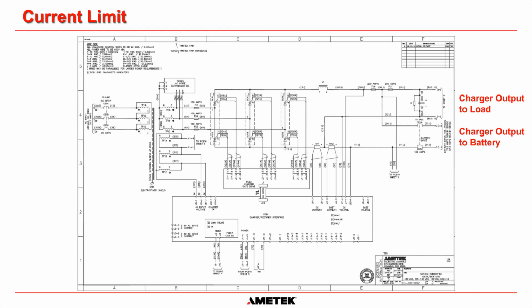And this last drawing here is from an AMETEK SCI UPS. And on our modern DPP UPSs, we actually now have two current limits. We have a current limit here, so that's actually the current limit for the overall DC of the system, and then this shunt is measuring the current to the battery. So we have two on our DPP UPSs. We have a two-stage current limit. We have an overall charger output current limit, and then a battery current limit. Okay.